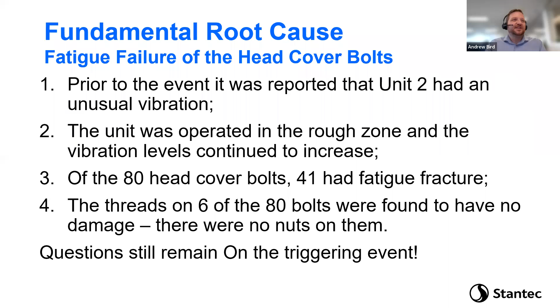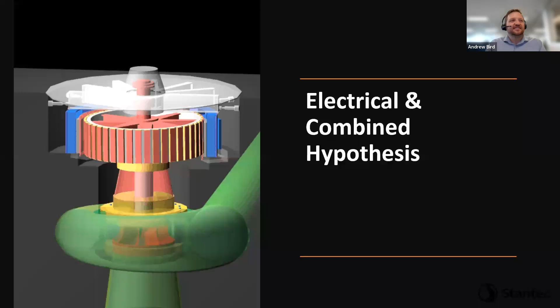Okay, thanks for that. That's probably more of a statement than a question, but it holds true to a number of failures. So many failure investigations show the operating team silencing alarms as part of the cause. Operators deal with nuisance alarms daily, which creates a habit of silencing them, which can be very annoying. These false alarms should be minimized to prevent this.